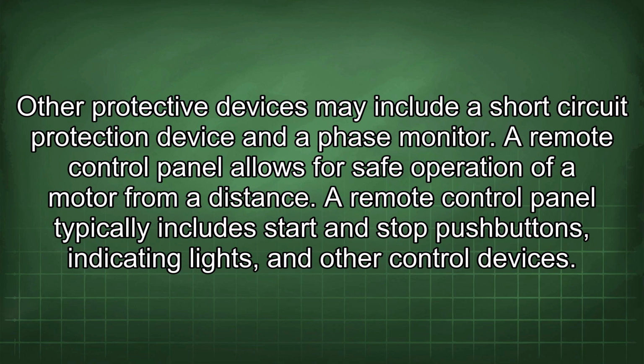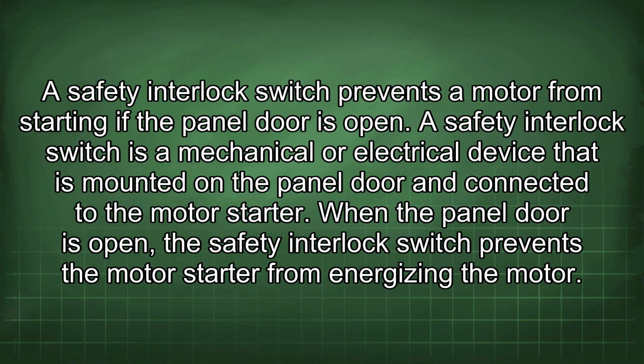A remote control panel allows for safe operation of a motor from a distance. A remote control panel typically includes start and stop push buttons, indicating lights, and other control devices. A safety interlock switch prevents a motor from starting if the panel door is open. A safety interlock switch is a mechanical or electrical device that is mounted on the panel door and connected to the motor starter. When the panel door is open, the safety interlock switch prevents the motor starter from energizing the motor.